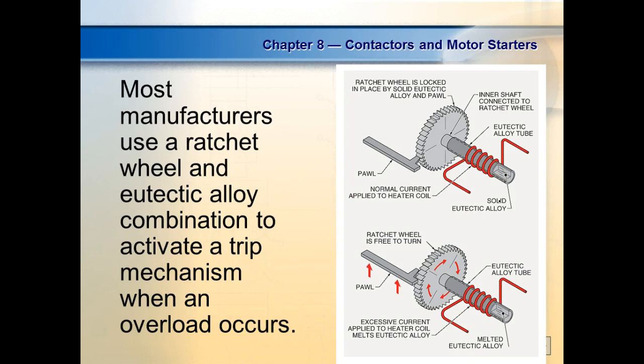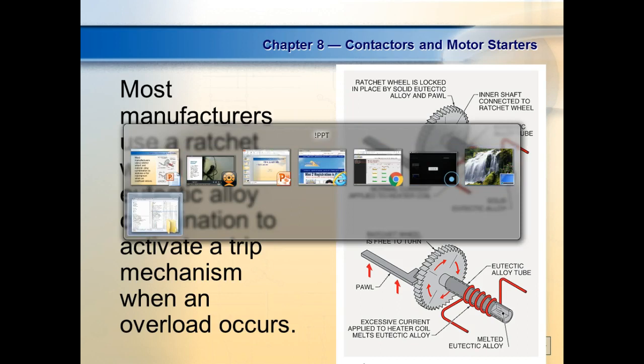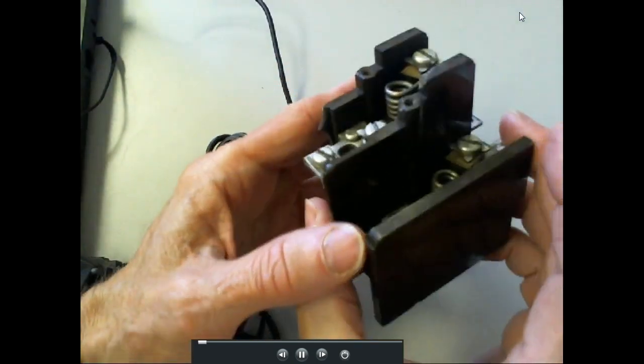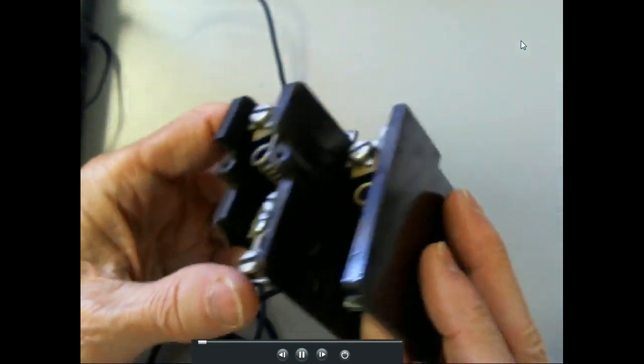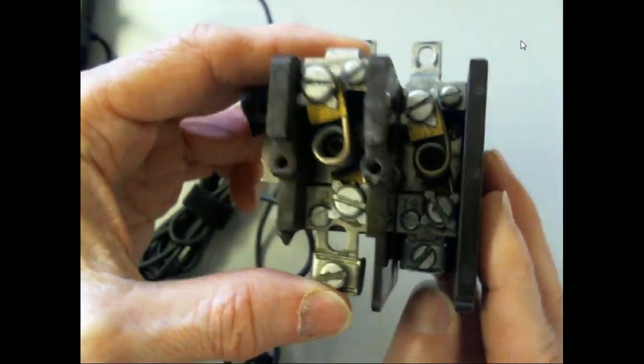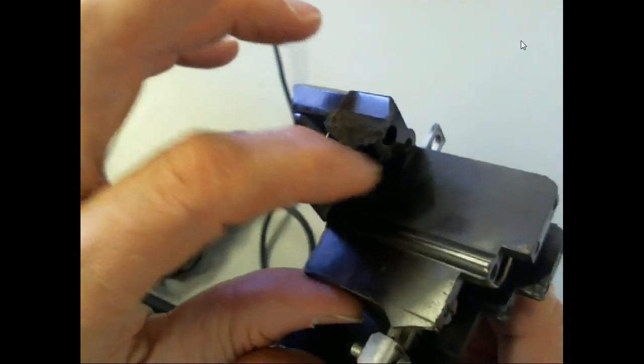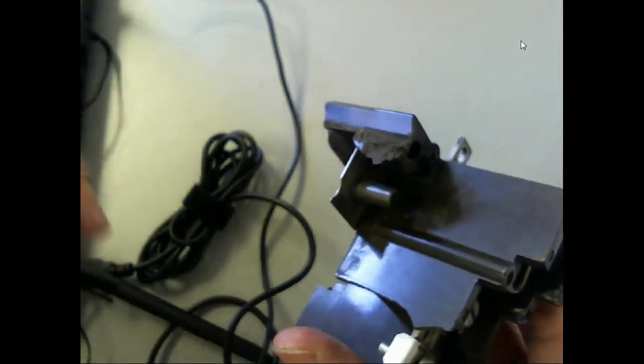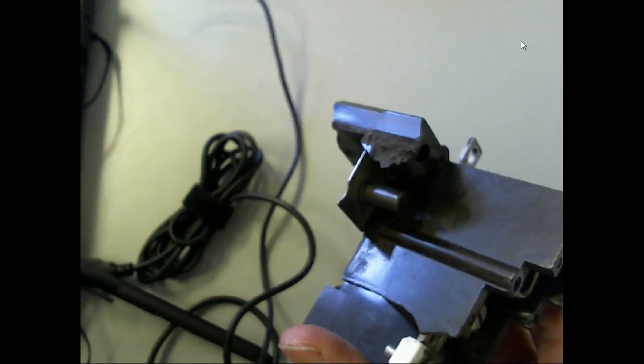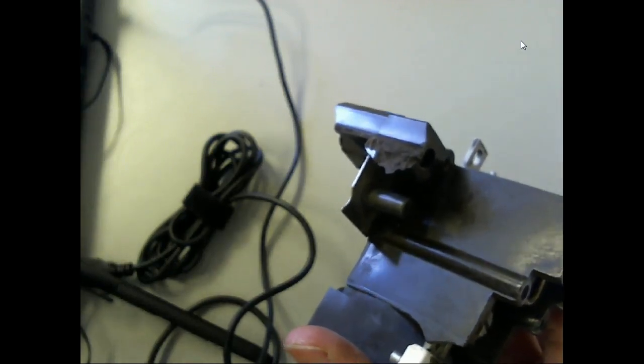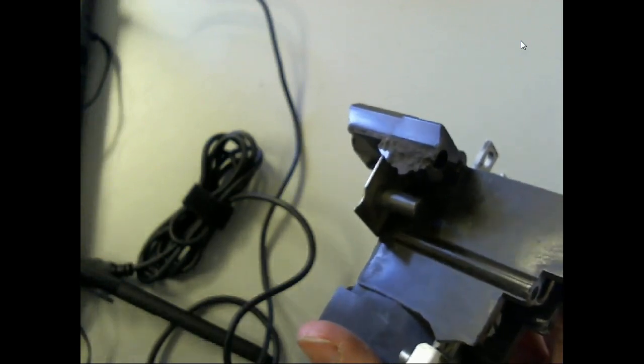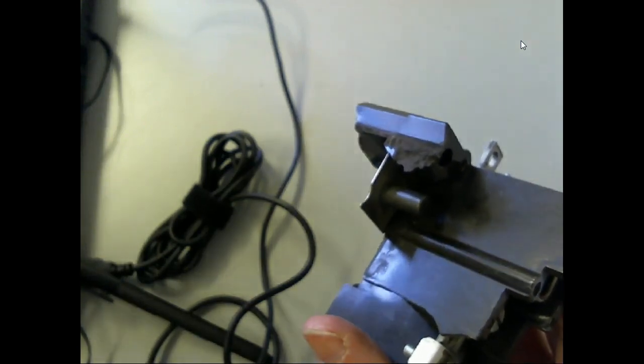So these guys here work on a little assembly. It's a little ratchet assembly. Now, like I said, you're going to run into this. And I'll pass this around and let you see this. This is actually one that was dropped and got broke. So the heater coils, if I can get this up here, I don't have enough light, wrap around a tube. You can see this little tube right here. And this tube has solder in it. So when solder is cooled, it turns into a solid, right? You understand? And then we heat it up. All metals have what we call a melting temperature. And when you get the metal up to its melting temperature, it turns into a liquid, right? You understand?